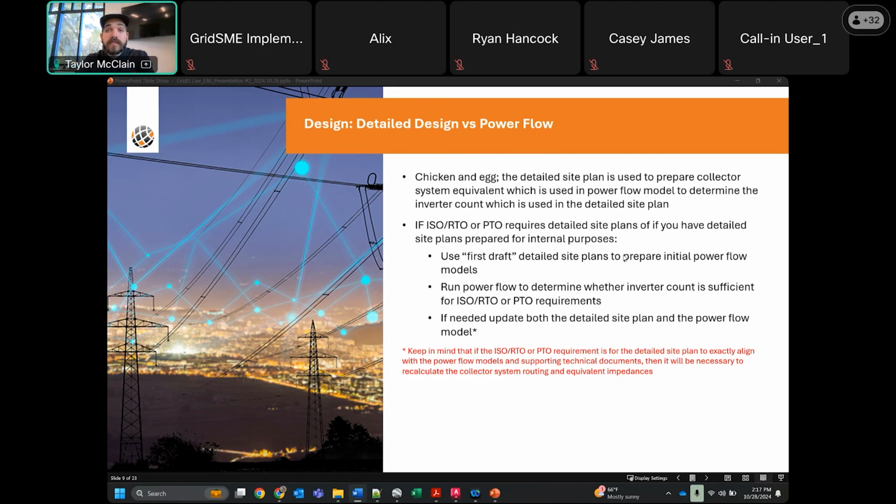It is certainly something that could be run to ground with an inverter manufacturer. Most folks don't have their PPC manufacturer in line in the early stages, so maybe that wouldn't be as pertinent. But so far, from a functional standpoint, I have yet to see any issues. And as well as from a utility input standpoint, we have not received any deficiencies specific to pairing up to specific inverters. So I would say in most cases, you're probably fine to go with either pair that you like.